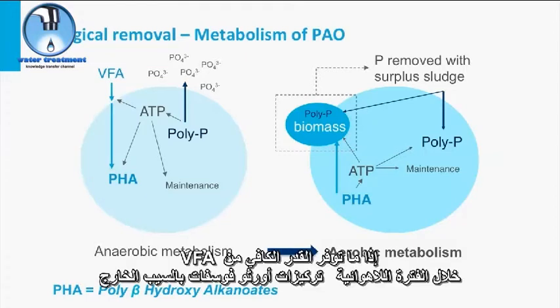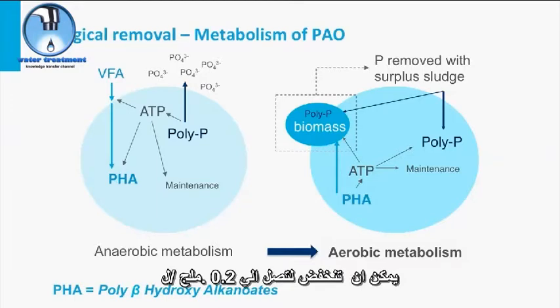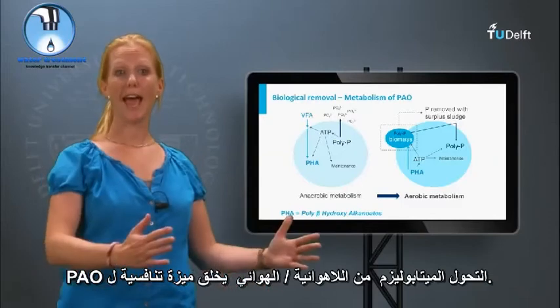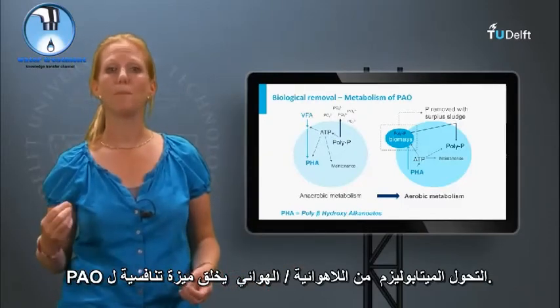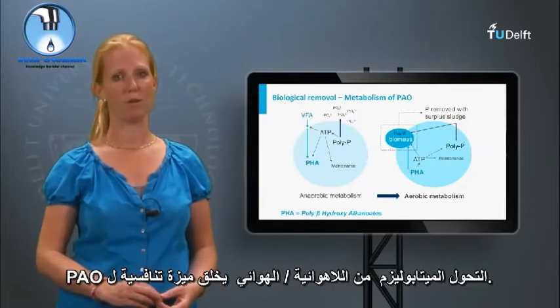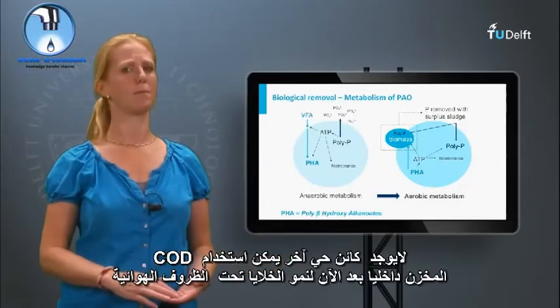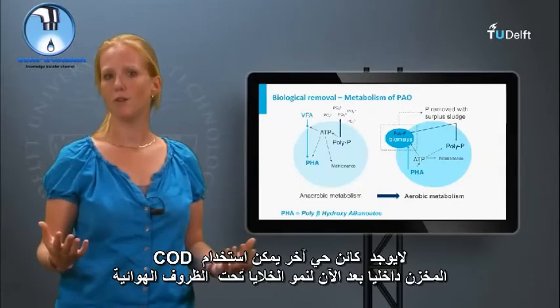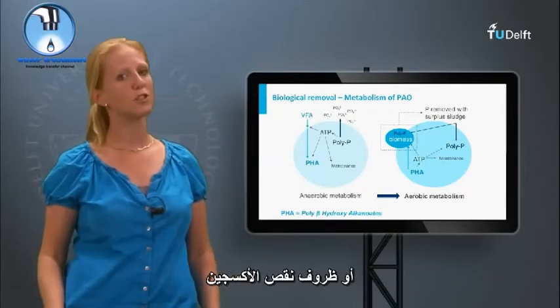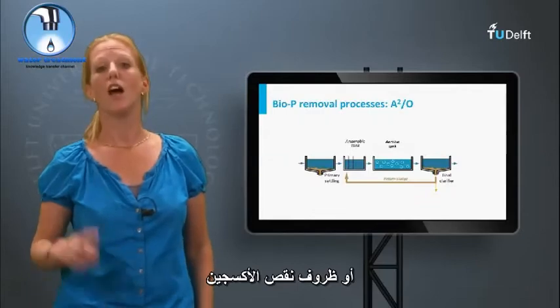If enough VFA is available during the anaerobic period, effluent orthophosphate concentrations as low as 0.2 mg P per liter can be reached. Switching between anaerobic and aerobic metabolism creates a competitive advantage for PAO, as no other organism can use the internally stored COD anymore for cell growth under aerobic or anoxic circumstances.